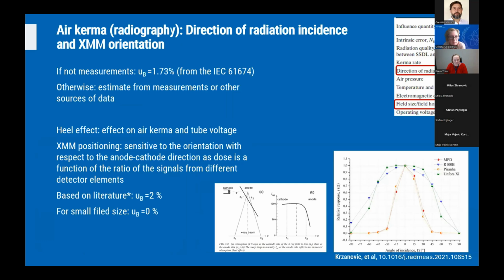Another important aspect that should be considered when using X-ray multimeters is their orientation and the direction of the radiation incidence. These instruments are basically designed to be used in the perpendicular geometry. So basically they would have a correct readout only if the X-ray beam axis is normal to the entrance surface of the dosimeters. According to a recent paper, the correctness of the indication of radiation dose with XMMs would be okay for angles of plus or minus 15 degrees. However, depending on the design of the XMM, this angular dependence might be different and more pronounced for the robust instruments compared to the small ones.